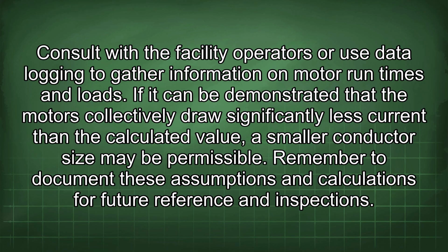Consult with the facility operators or use data logging to gather information on motor run times and loads. If it can be demonstrated that the motors collectively draw significantly less current than the calculated value, a smaller conductor size may be permissible. Remember to document these assumptions and calculations for future reference and inspections.